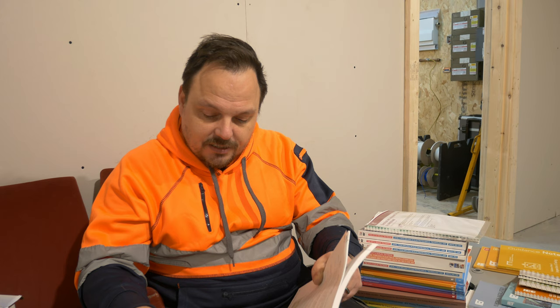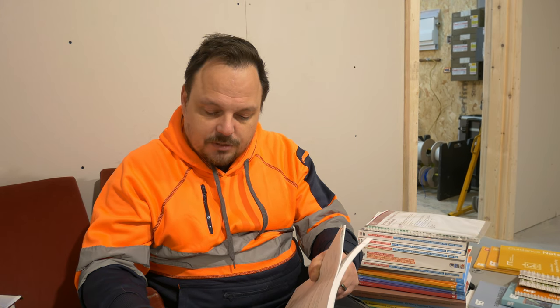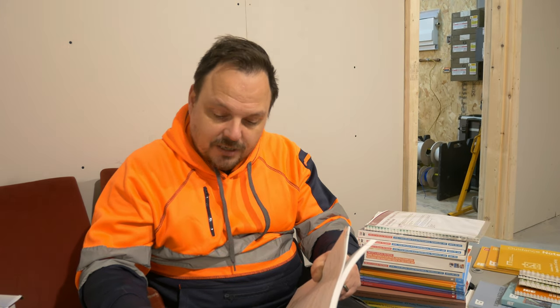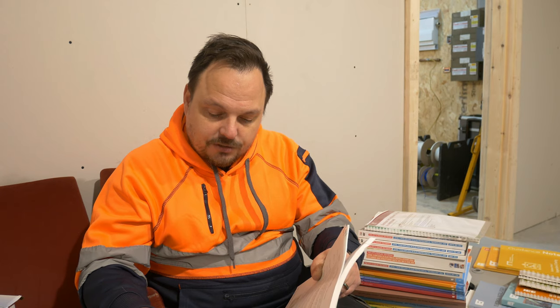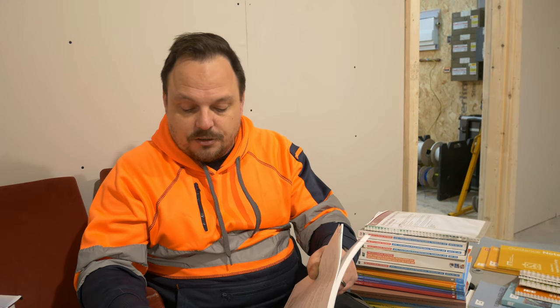So it says here, where the installation designer has selected cable tray for use as a protective conductor, which is permitted under certain regulations, it's described as an electrical continuous support system for conductors. The cable tray must meet the requirements of a protective conductor given in regulation 543.2.2 and will need to be connected with earth. So in short, you don't need to do it.